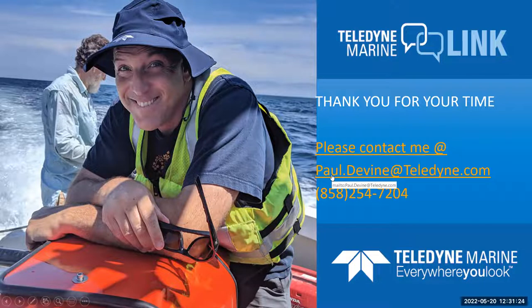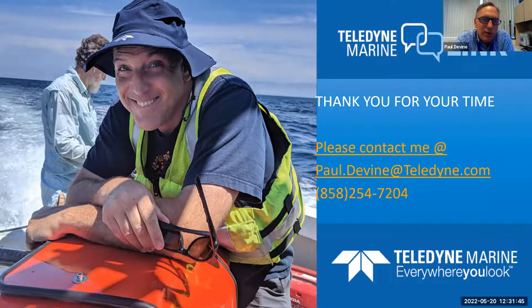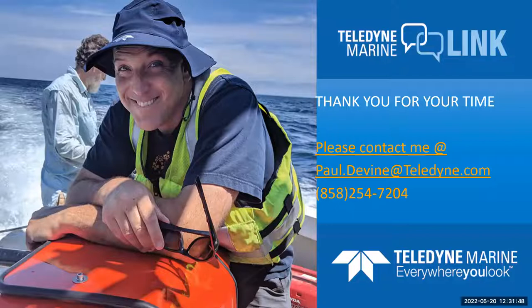So unfortunately, some of the problems that we have is we're limited by old AUV platforms and their data rates. So we actually can't record all the correlations and the echo intensities that we want to, because we really just have a throughput problem. The other problem we run into fairly often is possible hardware issues, especially after a really hard recovery. You were privy to the conversations we were having with Wilbur and used FFT tests and things like that for internal noise. But do you have any sort of flow diagram or guidelines in terms of what to look for in hardware issues specifically for the ADCPs?